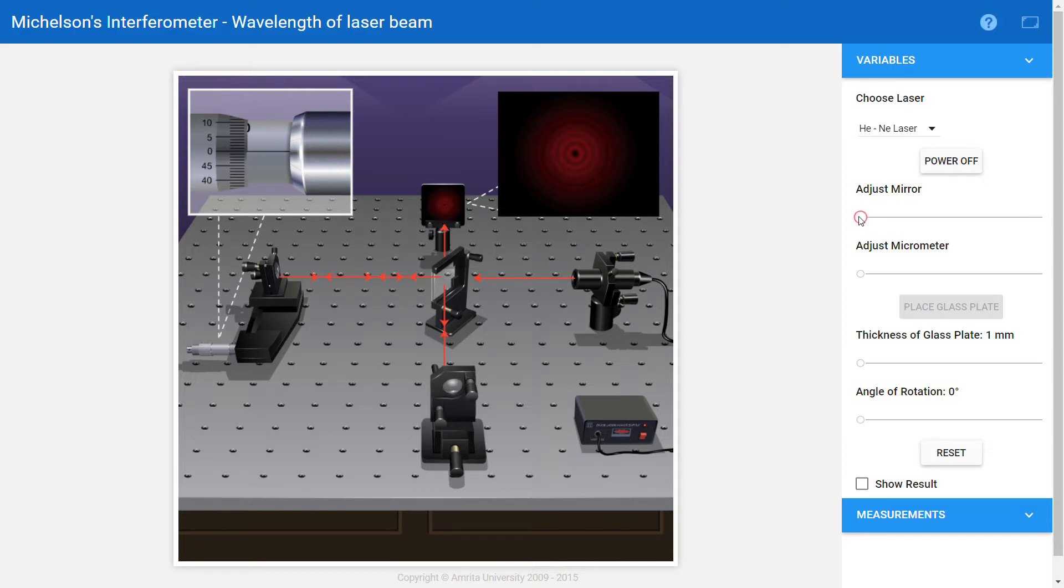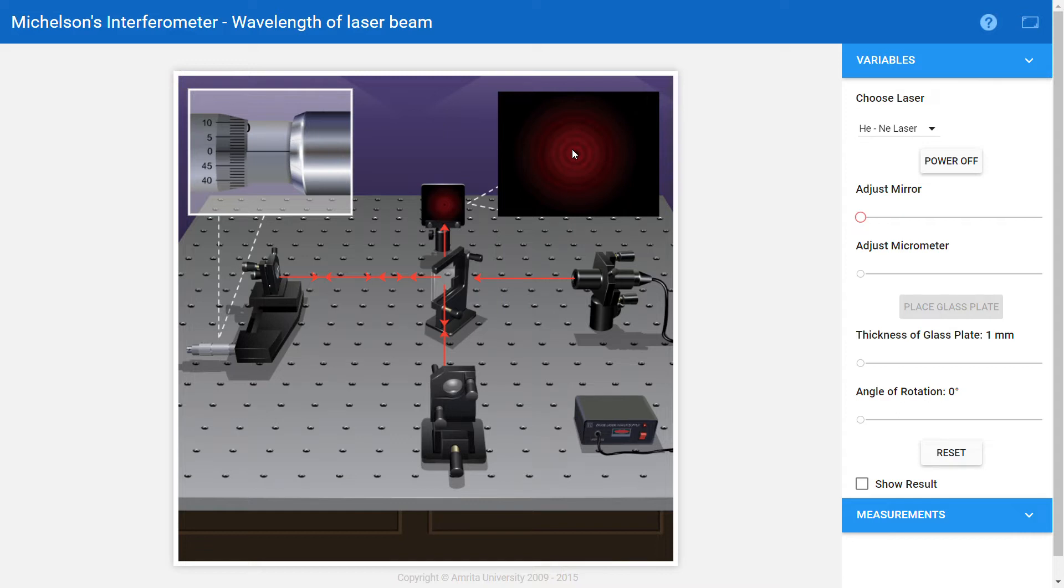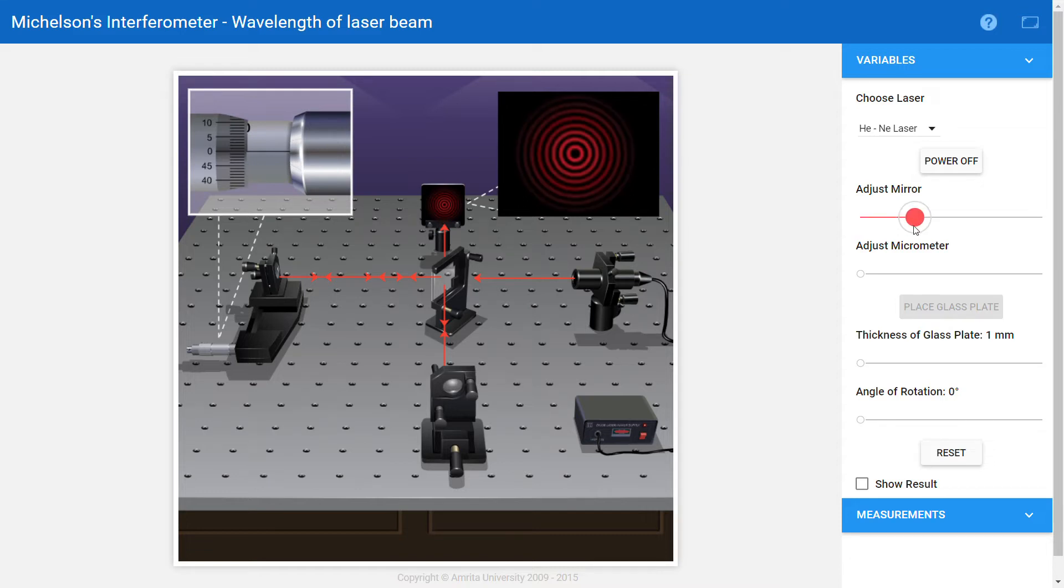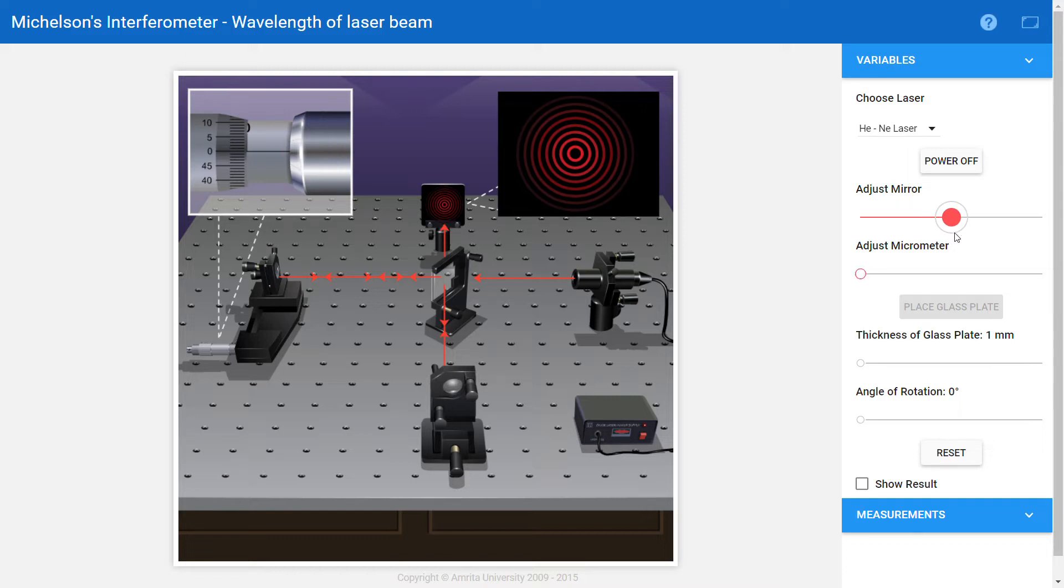Now we need to adjust the mirror. If you see the fringes here, it is not a focused image, so we need to adjust the mirror so that we will get the focused image on the screen. Unless you adjust the mirror to get a focused image, the adjust micrometer button or slider won't be active.